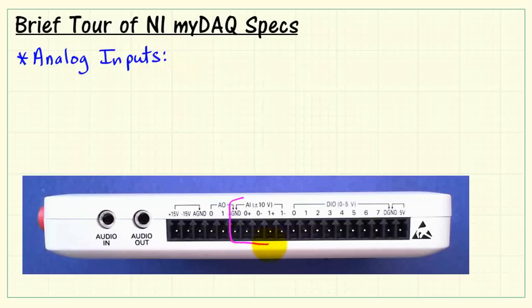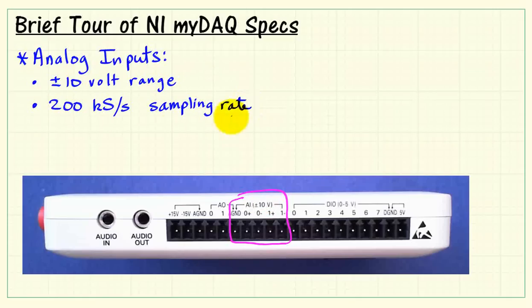The analog inputs are located right here. These inputs have a plus-minus 10 volt range. They are limited to plus-minus 10 volts, so make sure you do not exceed that voltage range. 200 kilo samples per second sampling rate, 16-bit resolution, DC coupled, and they have in excess of 10 gigaohms for input impedance.